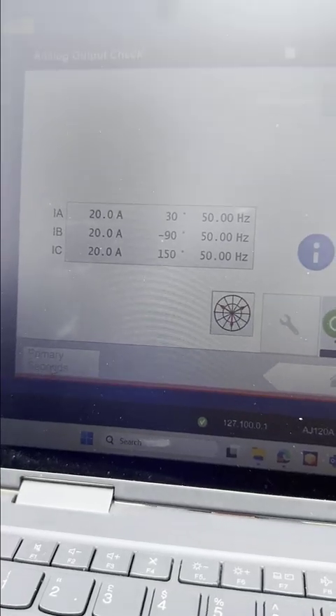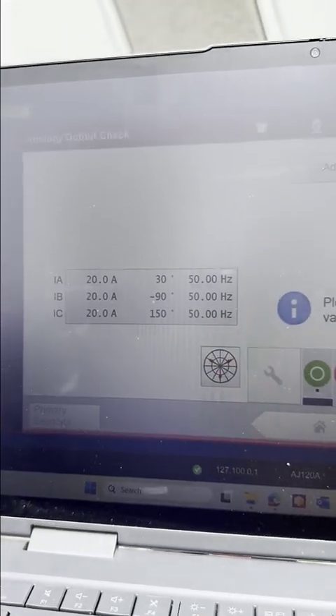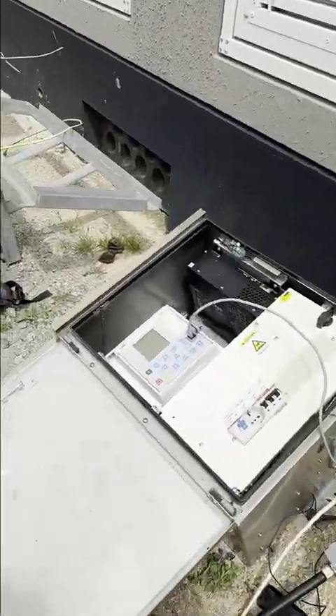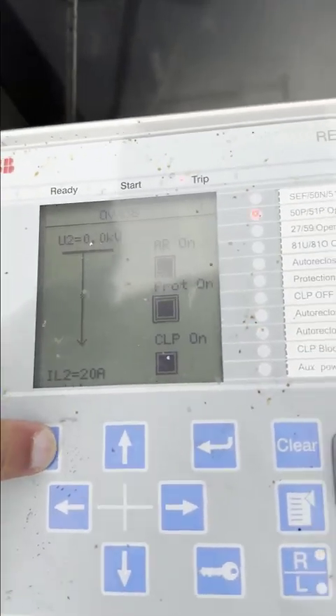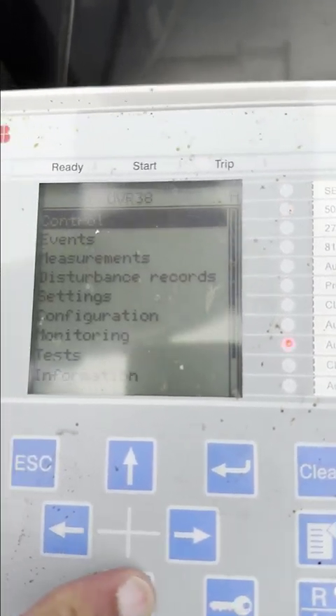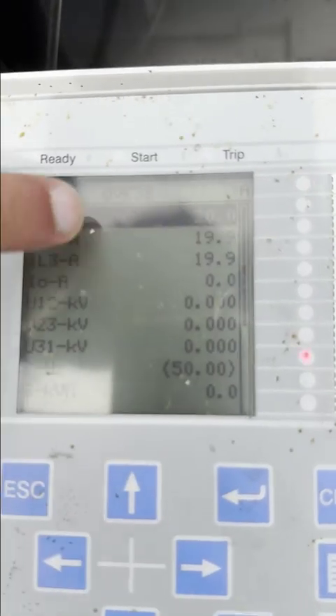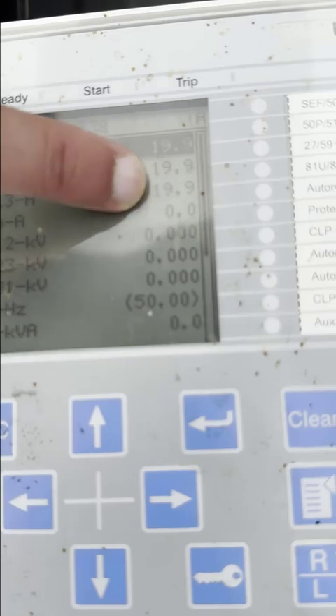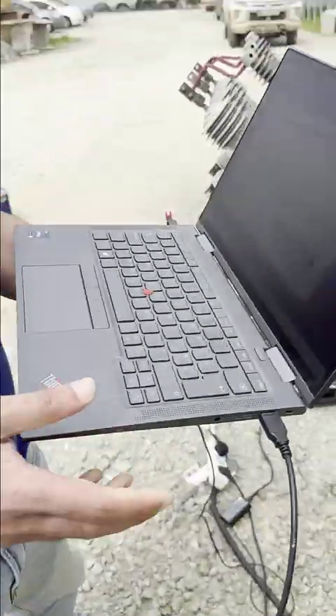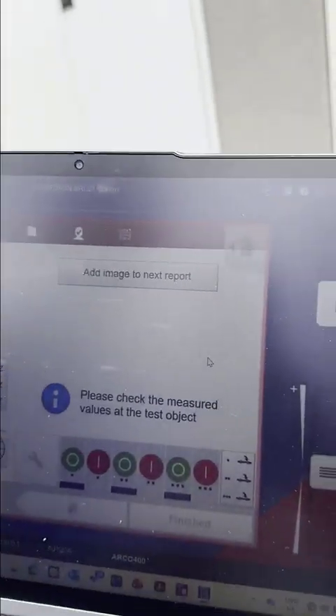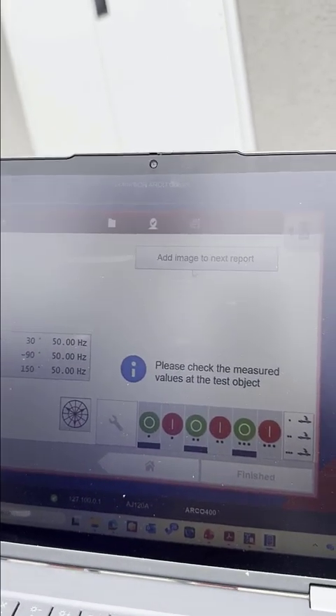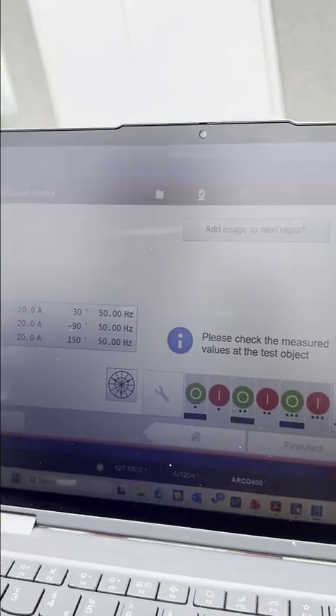Also the time can be displayed in seconds or in cycles. And now you can check the measurement from the relay itself. So IL1, IL2, IL3 is 19.8, 19.9, and 20. Also you can record it in a comment, or if you are connecting with the software, you can take a snapshot and you can add this image to be printed out in your test result.